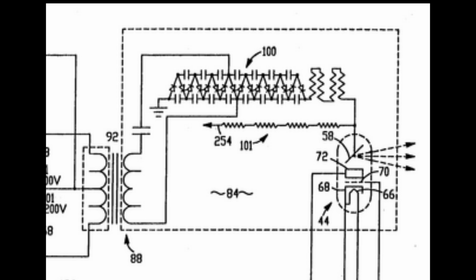Here's an image from one of the patent numbers referred to on the label. There is a voltage divider inside which goes to that terminal, but interestingly the main voltage multiplier is fed from the centre. Not something I've seen before. It might be quite common. I've not really looked at too many of these things, because long voltage multipliers get increasingly inefficient because of things like stray capacitance and so on. So what they've got is this floating drive from the transformer which they're feeding into the centre of the voltage multiplier, so you're effectively generating a bipolar supply and then grounding the negative end to produce the high positive voltage.